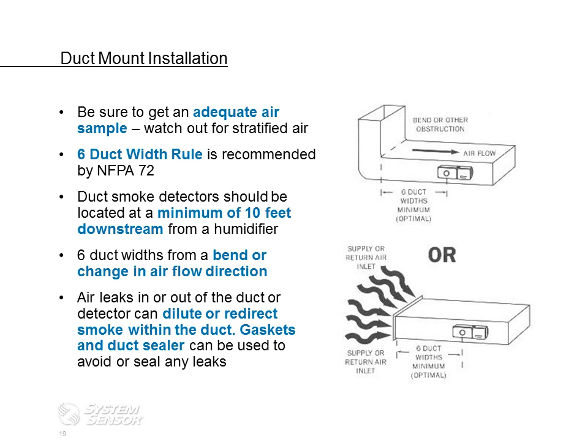Duct smoke detectors should be located a minimum of 10 feet downstream from a humidifier. Further is better because anytime you're introducing humidity into the ductwork, in most commercial spaces now and residential spaces, they have system humidifiers, water and electronics don't mix very well. So the further away you can get it from the humidifier, the better off you'll be.